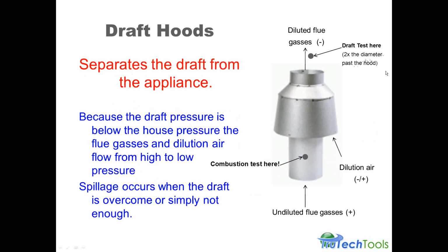Here's a quick illustration of a draft hood. It's something you may or may not encounter in your testing, but in this case it serves to draw the line between different areas where you're making samples and doing tests. So the undiluted flue gases would be coming up through the bottom portion of a draft diverter or the draft hood. You'd make the combustion test in this area here. This is where we're talking about the undiluted flue gases, which are under a positive pressure moving through the system. The dilution air can move through with a positive or a negative pressure. It can either be pushed through or pulled through. And for the diluted flue gases here, you would be measuring a negative pressure because you'd be measuring the pull, the draw that they have to move flue gases up.